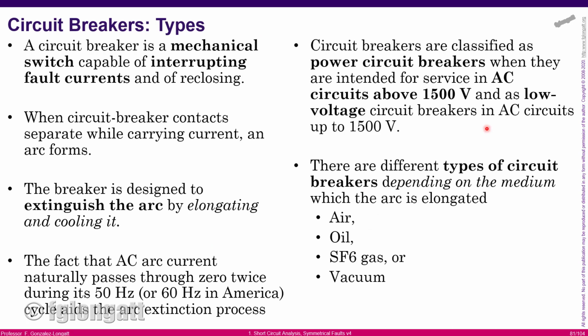The first thing that you must understand is that the circuit breaker is a mechanical device. Well, to be honest, it's an electromechanical device, because it's using mechanical forces to try to stop and interrupt fault currents, and that is electricity. The circuit breaker is trying to stop the short circuit current, opening the contacts.